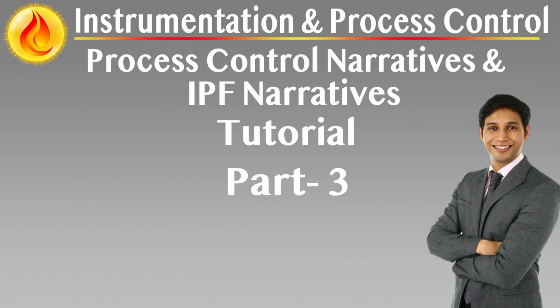Functional relationships between inputs and outputs. Each IPF must define the logic relationships that connect initiators to final elements. This includes voting schemes, e.g. 1oo2, 2oo3, conditional logic, e.g. and/or gating, permissive or interlock conditions, delays, filtering, or signal validation methods. These relationships must be clear and support deterministic safety logic. If implemented in logic diagrams, e.g. FLDs or cause and effect matrices, those diagrams must be referenced.